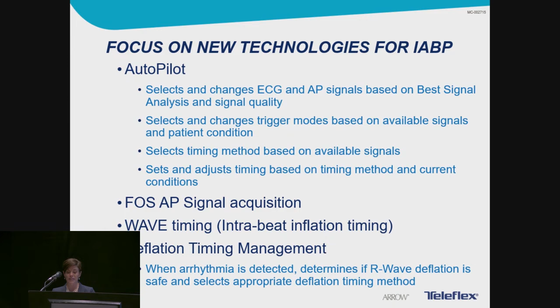And last but not least, when an arrhythmia is detected, the pump assesses the time available and the time needed to deflate the balloon at least 70%. Now, the deflation timing method is selected based on this algorithm, and the assessment is dynamic as long as an arrhythmia is present. Now, we start to look at our pressure volume planes and really dive into what we want and expect a balloon pump to do for our patients.